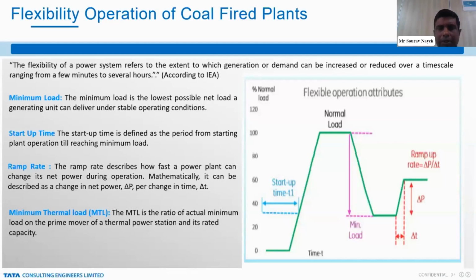Till now we have talked about the different reasons for heat rate deterioration and the corrective actions in an ongoing thermal power plant. Now today's need is to operate as the renewable energy sources are increasing. The share of power from the RE sources is increasing, and coal-based generation is reducing. The main aspect of the thermal power plant is to operate with flexible operation down to a minimum load. Now, what is the flexible operation of the thermal power plant? We have captured it in this diagram.